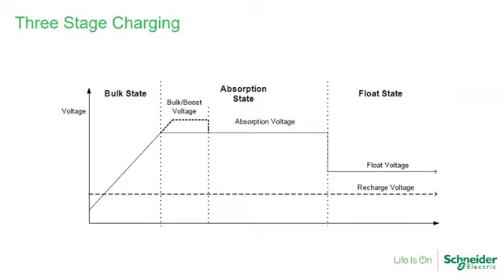The solar charge controller is going to charge the batteries in this very typical 3-stage charge. So every day, what we should see in a properly sized system is that the solar charge controller wakes up in the morning, depending on the solar irradiation and the angle and what time it'll wake up, and it will start charging the batteries in this first stage, which we call bulk stage. The voltage and the current are increasing until they reach a preset set point, which is programmable.